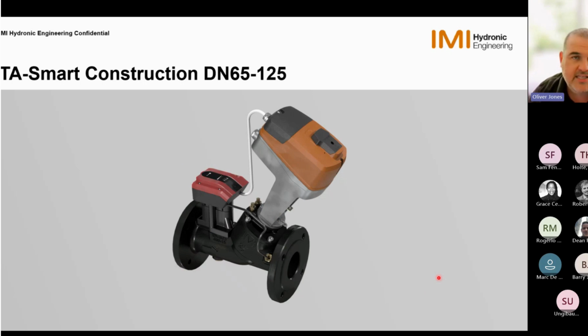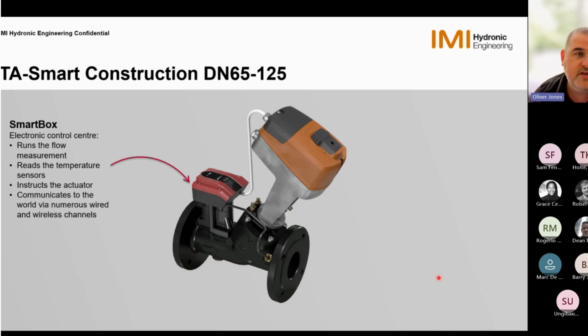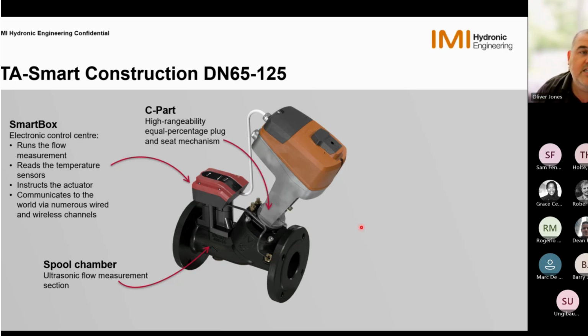So if we then look at our TA Smart construction for the DN65 now up to 125, again, exactly the same things. We have the smart box, which is positioned on the back. So again, this is running all of our flow and temperature sensors and telling the actuator to move the control plug up and down. And then our spool chamber. So again, our ultrasonic flow measurement device is in this bottom section. So that's constantly monitoring and measuring flow and recording that within the smart box.